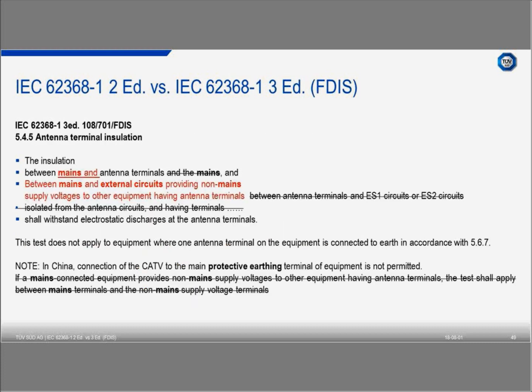This is also a topic, this point coming with the antenna terminal insulation. The point is that this was transferred from the 65 and it was transferred in the wrong way. So this is the correction. We have to check between mains and the antenna and between mains and external circuits. We have to look carefully at what's going on, but this is now the correct part from the 65, which was wrong here and leads in the second edition to maybe wrong results if you do this.